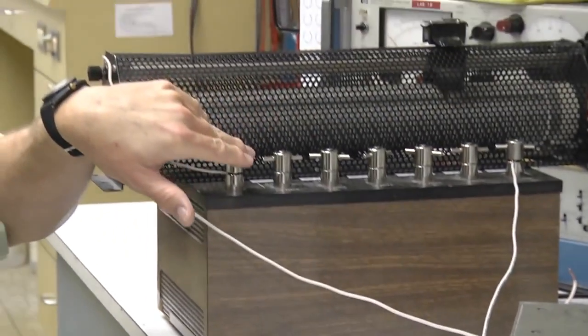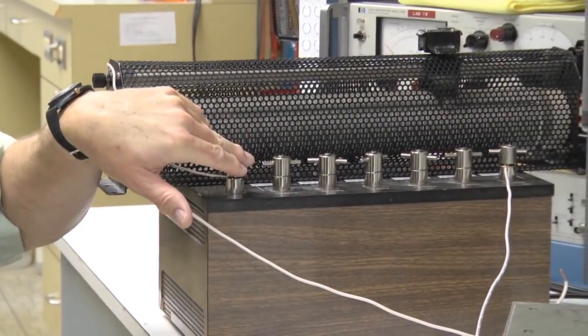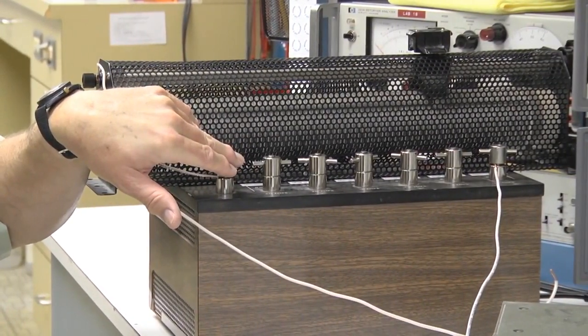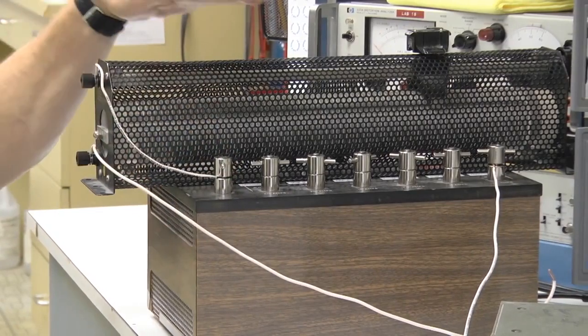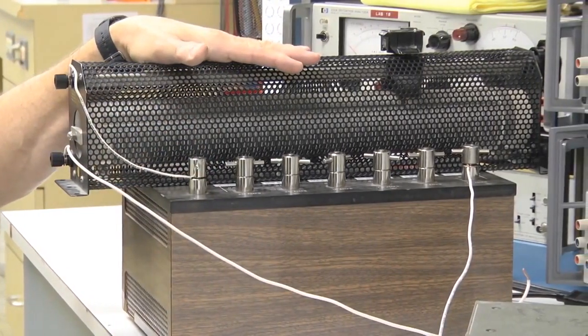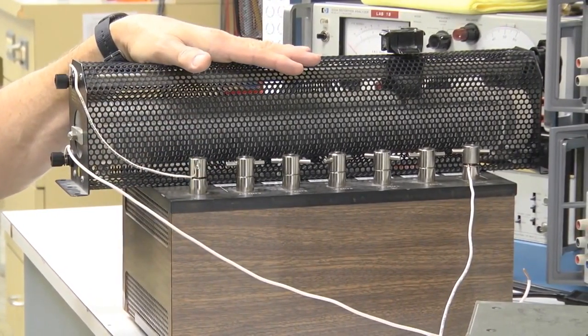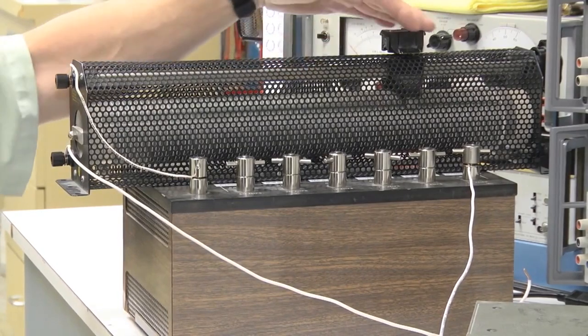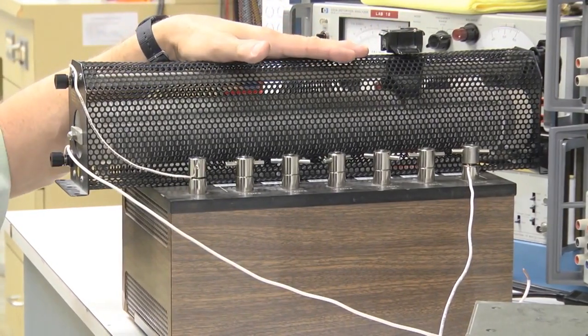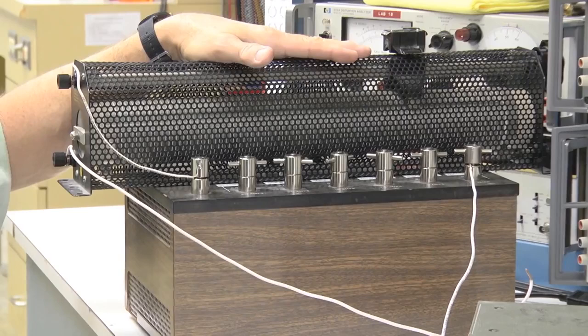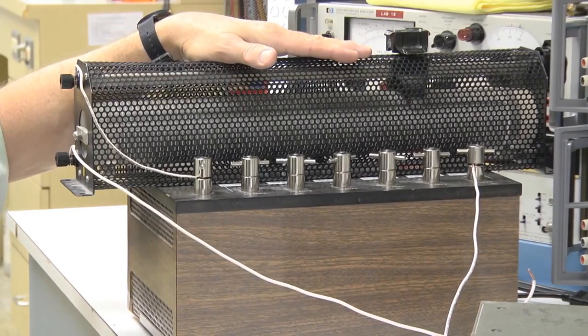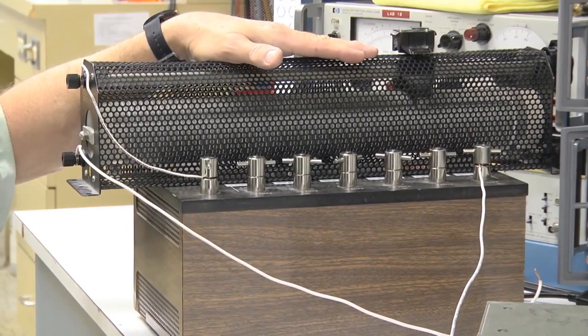In calibrating it, we're going to be using the Guildline current shunt, which is our current standard here at Boise Calibration Service. We'll also be loading the power supply down with the Biddle load resistor, and it's a variable resistor, and it moves back and forth, tapping off various resistances so that we can load the power supply down to as close to full rated output as we can.